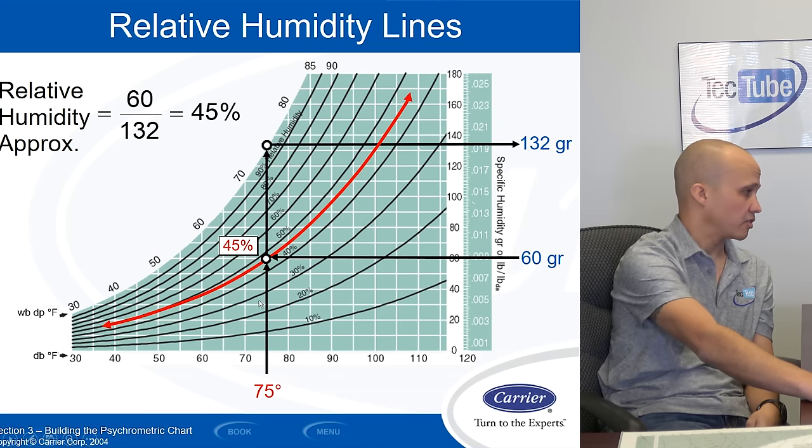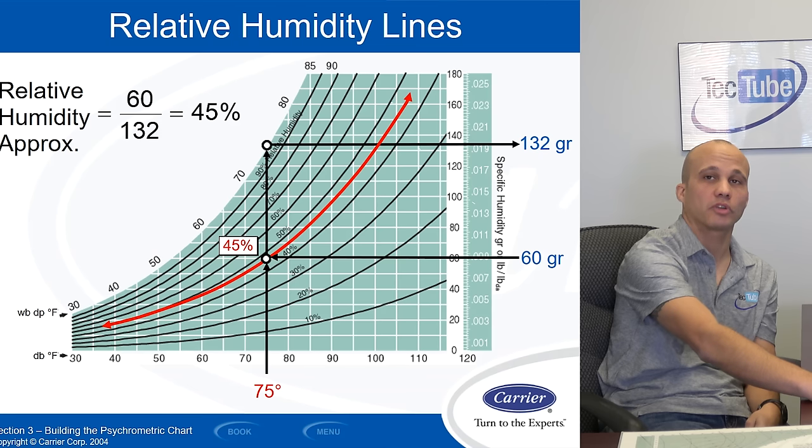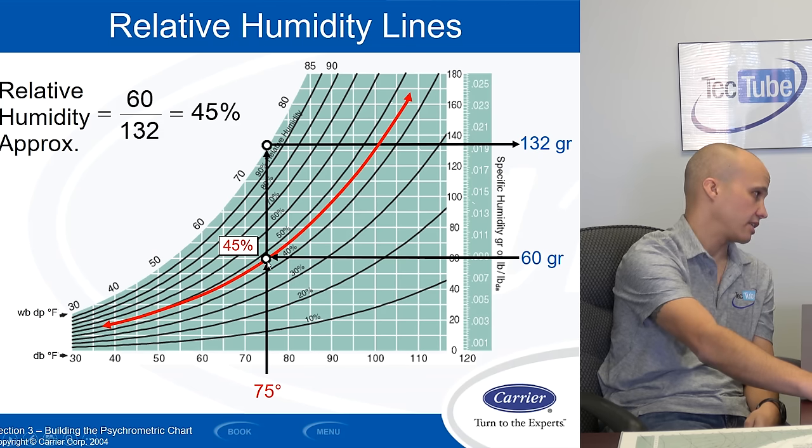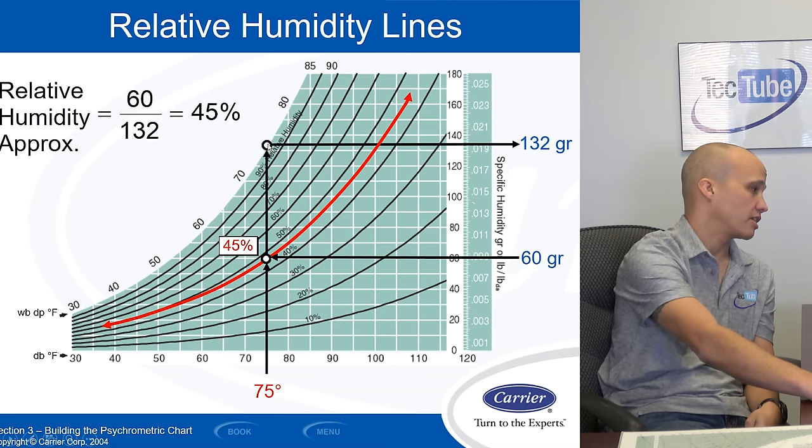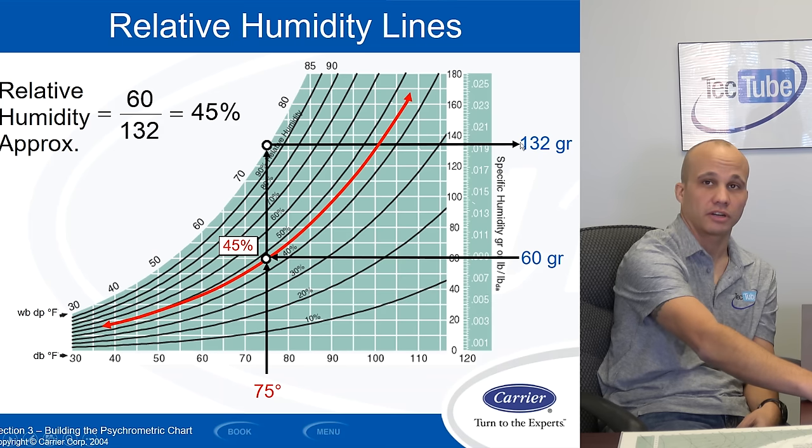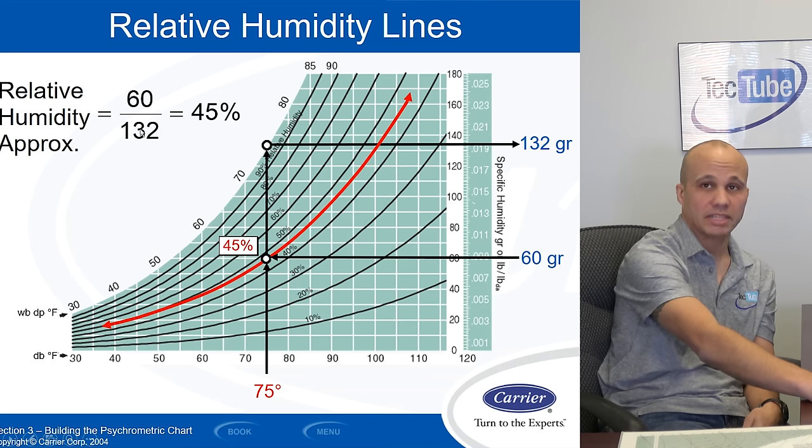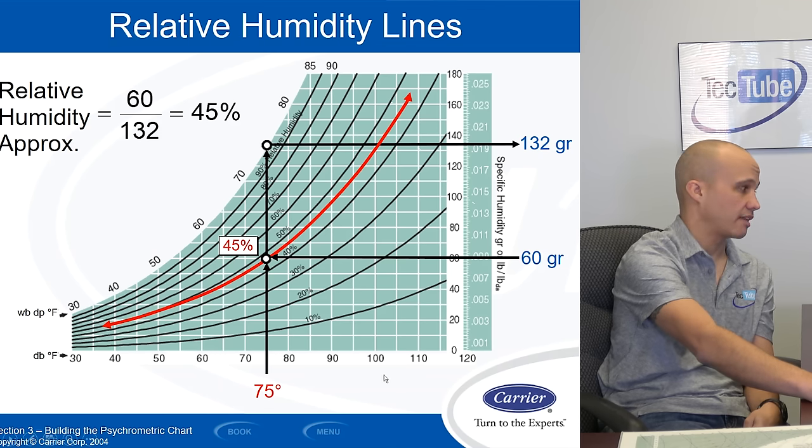So I want to figure out the relative humidity. I got my 75 and 60 grains. If I draw the line straight up and say, well, at 75 degrees, how much moisture could I hold before there was a condensation problem at 75 degrees? So go all the way up to 100% humidity. And I read it across, I could hold 132 grains of moisture. But I only have 60. So I have 60 out of a maximum of 132. That's 45% relative humidity. So that's how I'd be reading that.